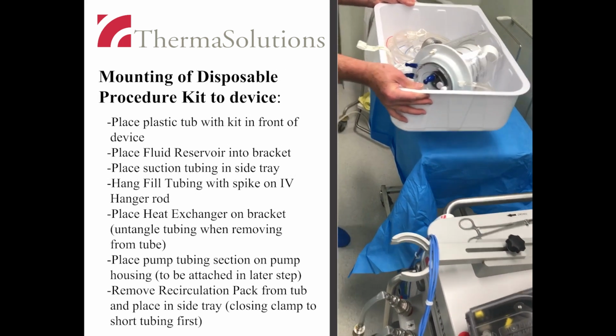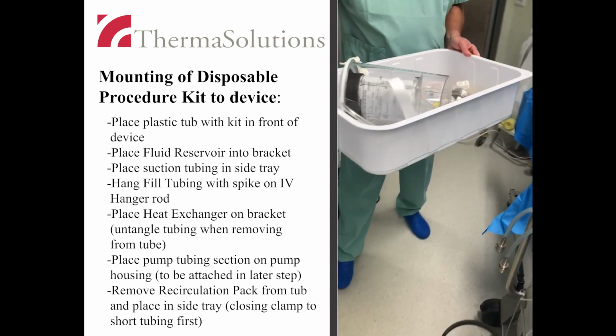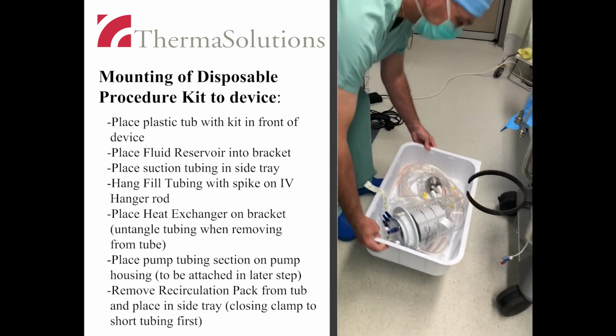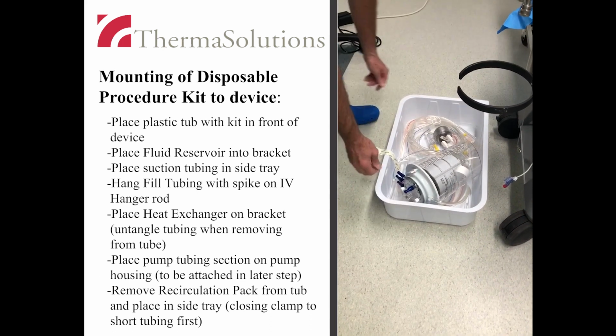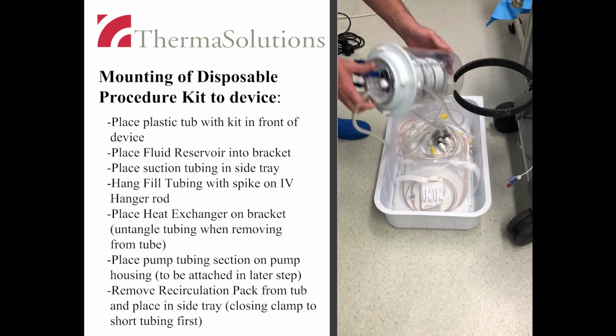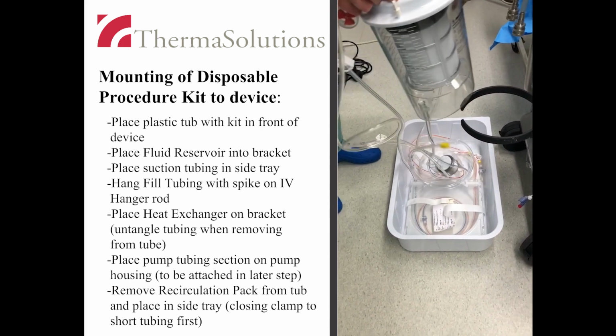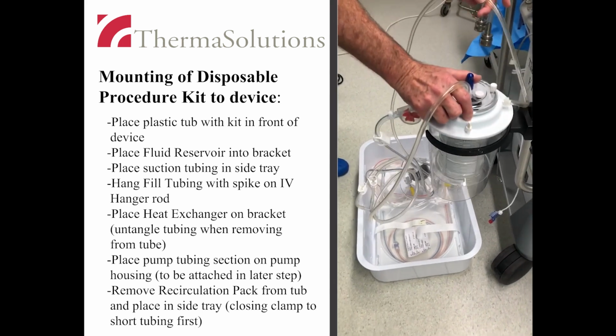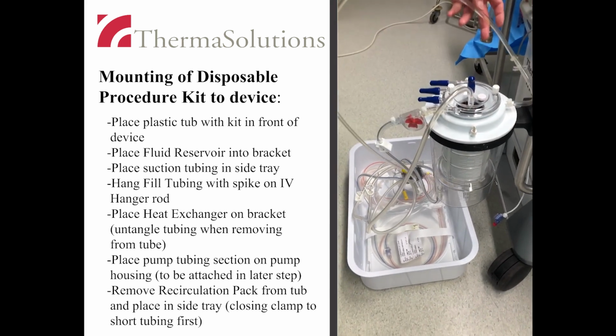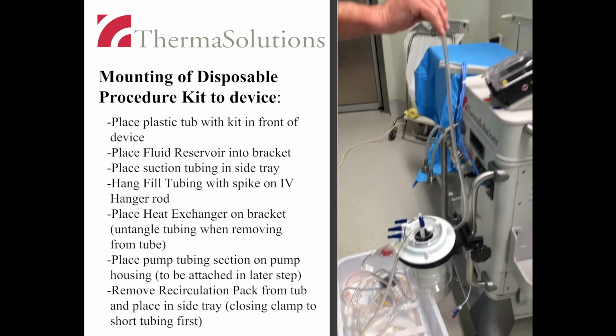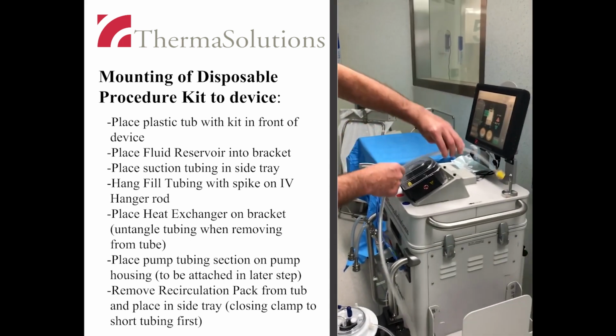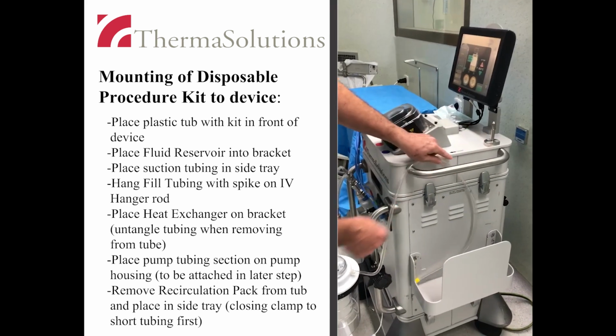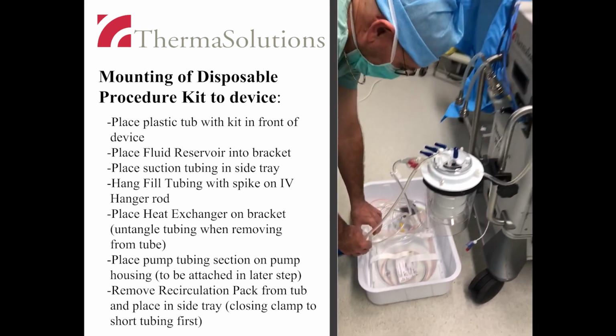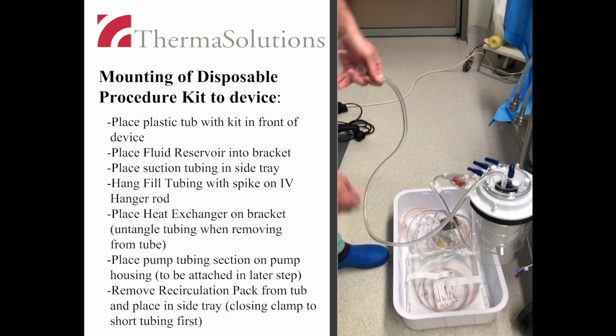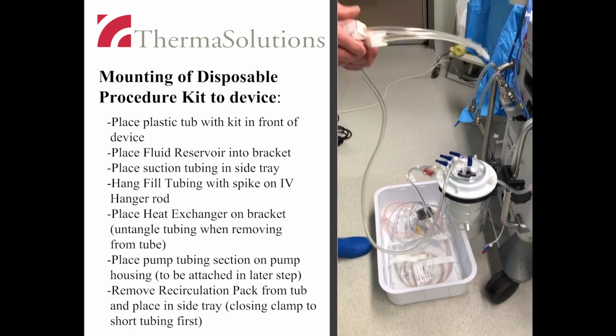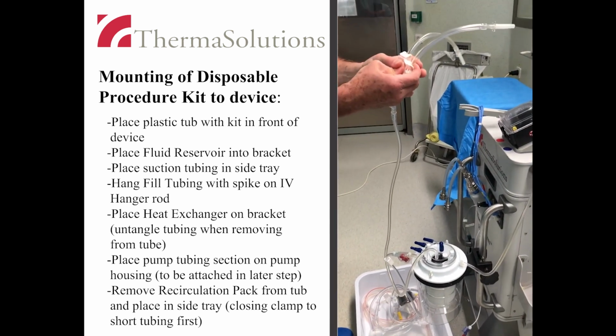Here are the steps for mounting the TSP procedure kit. First, place the plastic tub in front of the device. Remove the fluid reservoir and place it into the black fluid reservoir bracket. Place the tubing for suction in the side tray. Hang the fill tubing with spikes on the IV hanger rod and clamp both the fill tubing lines until needed.